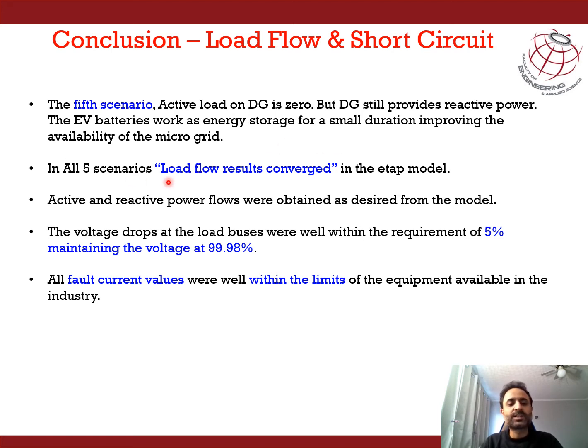So in summary, we can say that for all five scenarios the load flow results converged. We were able to see the active and reactive power flows as desired from the model. In all the cases, we were able to maintain the voltage level within the 5% drop, that is, more than 95%. In fact, we were able to achieve 99.98%. And also, the fault current levels at various buses were within the limits of the equipment which is available in the market. As a result, with these fault level values, we can put up any system available in the market and commission it for the Ramea Islands.